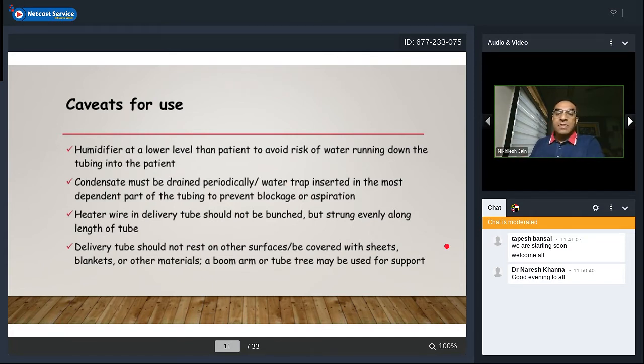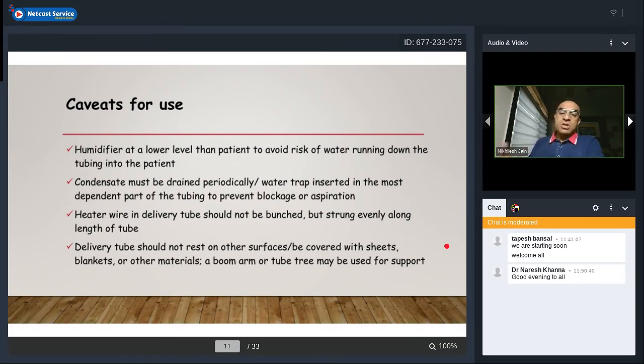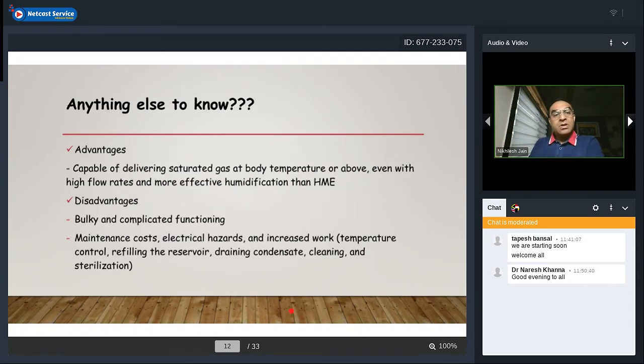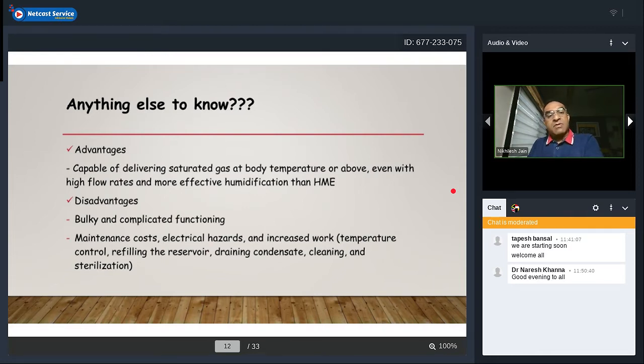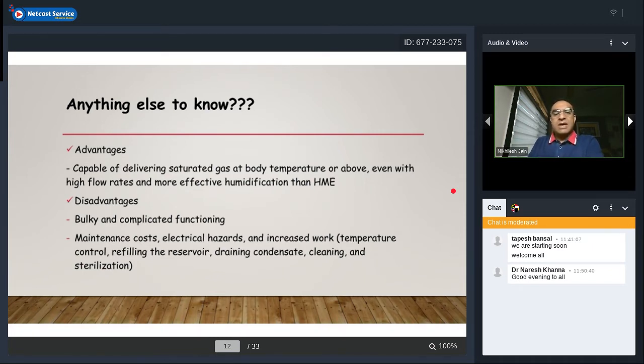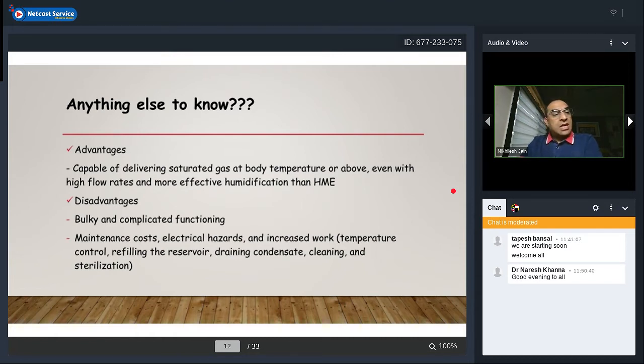If there is a heater wire in the delivery tube, it should be strung evenly along the entire length — not bunched. The delivery tube should not rest on other surfaces or be covered with sheets or blankets; a boom arm or tube tree can be used for support. Advantages of active humidifiers include capability to deliver saturated gas at body temperature or above, even with high flow rates — more effective than passive devices. Disadvantages include being bulky, complicated to operate, requiring maintenance, electrical hazards, and increased manpower for temperature control, reservoir refilling, condensate management, cleaning, and sterilization.